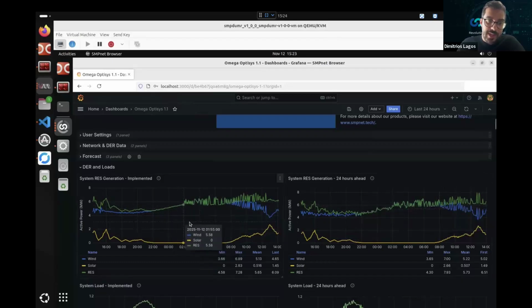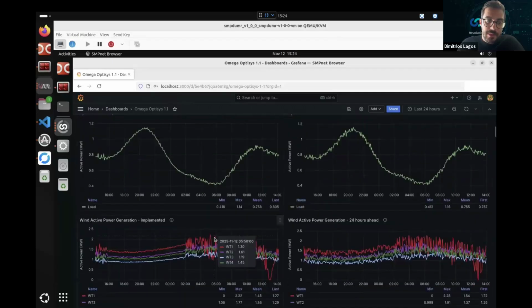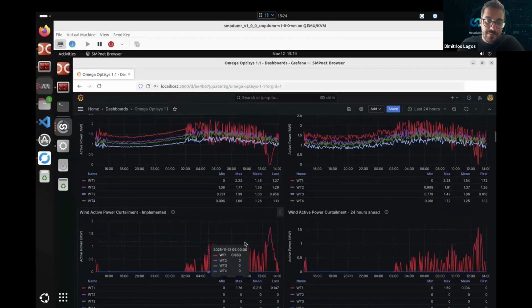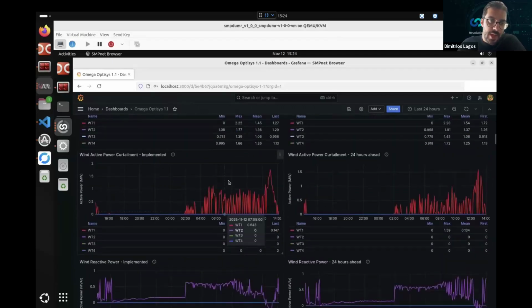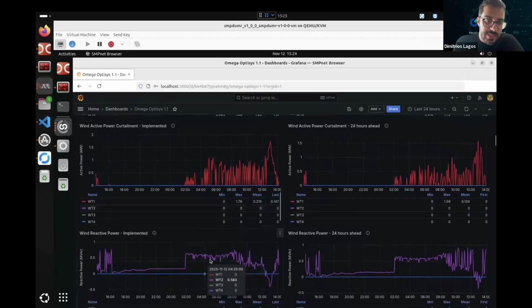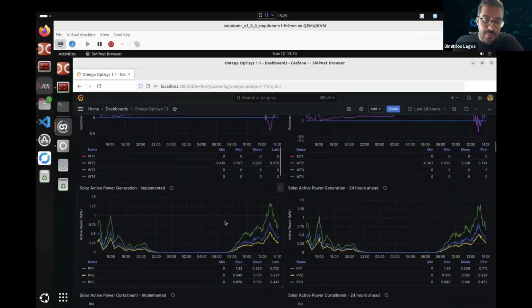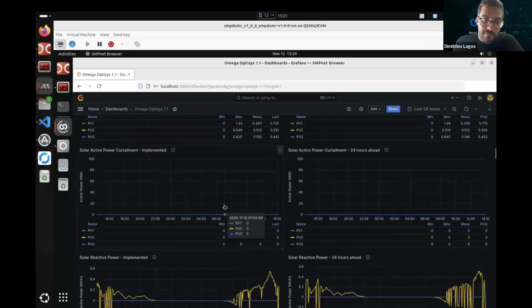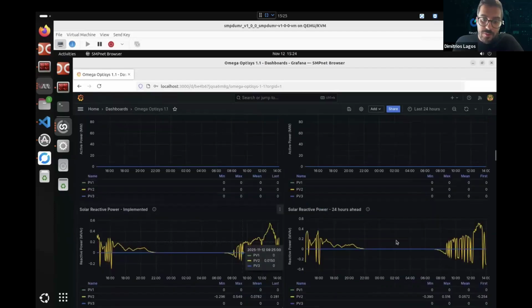So we see the total generation of renewables, solar and wind, and the system load. We see the wind turbine active power generation and curtailment. We see that Optisys resolves issues, either congestion or voltage issues in the network, by controlling active power of DERs in this scenario, or reactive power. We see here that there are several cases where it has issued curtailment for the wind turbines to resolve an issue in the network. And we also see that it has issued reactive power commands to support the voltage in the system. The same goes for the photovoltaics. No curtailment for the photovoltaics, but there is a reactive power dispatch, and a reactive power dispatch is also being scheduled for the next 24 hours.